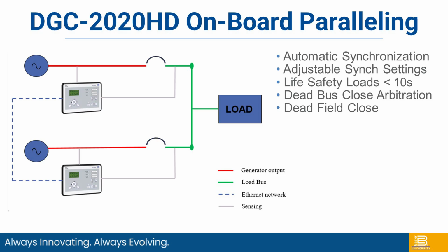It's an individual generator circuit breaker, and then supply and a load. We have both dead bus close arbitration, which means the two DGCs, or multiple DGCs, will talk back and forth to each other. And if they all get the start signal at the same time, they make sure that only one tries to close the circuit breaker first, and then the rest of them synchronize to that live bus.